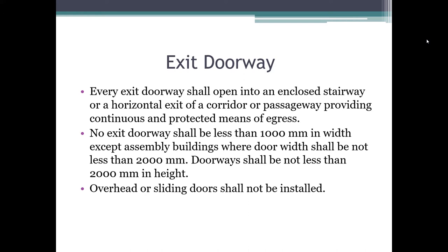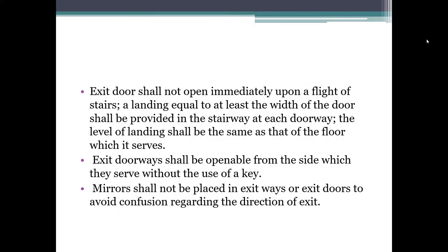Except assembly buildings, where the door shall not be less than 2 meters. The doorway shall not be less than 2 meters in height also. Overhead sliding doors shall not be installed. Exit doors shall not open immediately upon a flight of a staircase.